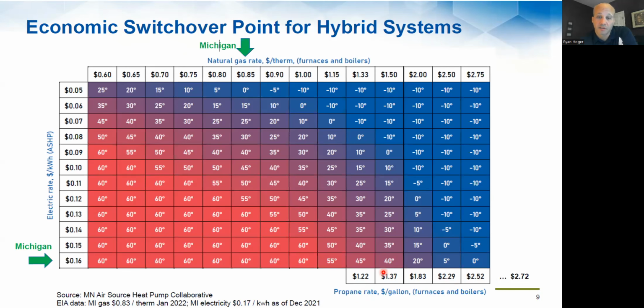Now, if you're paying something more ridiculous, like if you're on oil or propane and you're paying, you know, $3-4, now you're way over here on the chart, right? So let's just say propane, because it's on this chart, and let's say you have 16 cents electric and your propane's $2.50. At 0 degrees and below, you'd run your furnace, and above 0 degrees, you would run your heat pump. Now, if your heat pump has a thermal balance point of 20 in your application, it's as far as it can get enough BTUs for your building, then obviously you won't change over at 0. You change over at 20 because you can't make it down to 0. So for dual fuel systems, you will do the changeover at the higher of the thermal and economic balance points.